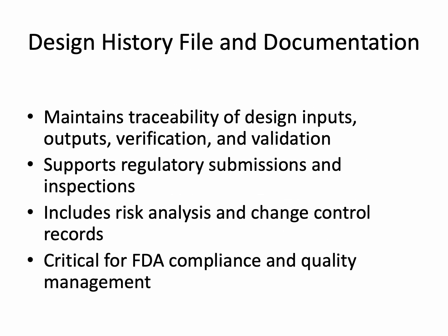The Design History File, DHF, is a central repository documenting the design process, verification, validation, and risk management activities. It maintains traceability of design inputs and outputs, including testing results, clinical evaluations, and design changes. Comprehensive DHF documentation supports FDA submissions, facilitates inspections, and demonstrates compliance with regulatory requirements.